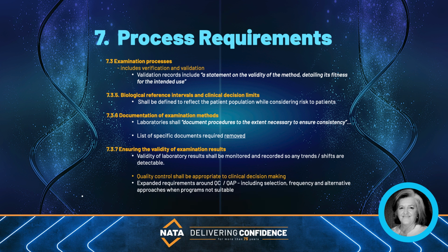Labs shall have a procedure for monitoring the validity of results. Data from monitoring activities shall be recorded in such a way that trends and shifts are detectable. Statistical analysis shall be applied to review results. Quality control material shall be appropriate to clinical decision making, and third-party material should be considered for ongoing monitoring. The material should remain fit for purpose and have a matrix as close as possible to that of the original patient samples. If QC material is not available, labs should consider using other methods, including retained patient samples.